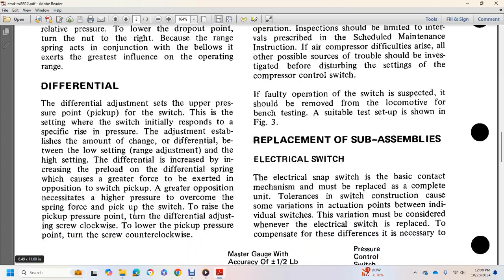Differential adjustments set the upper pressure point, the pickup of the switch. This is the setting at which the switch will initially respond to the rising pressure. The differential is the balance between the low setting, the range adjustment, and the high setting. The differential is increased with the preload on the differential spring, which causes a greater force to be exerted in opposition to the switch pickup. The greater opposition necessitates a higher pressure to overcome the spring force.